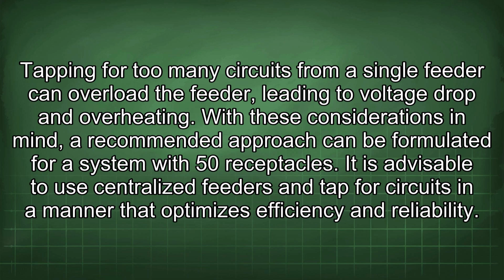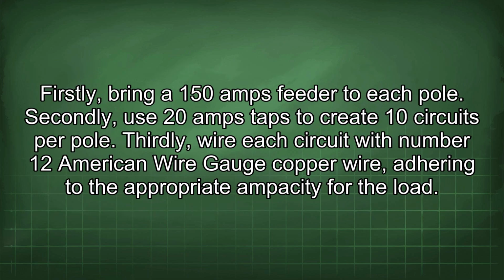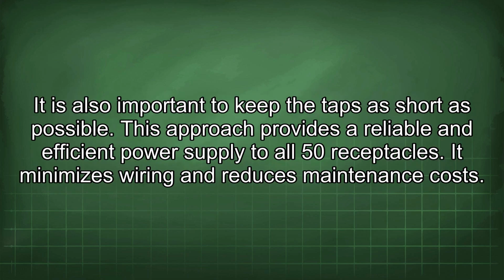It is advisable to use centralized feeders and tap for circuits in a manner that optimizes efficiency and reliability. Firstly, bring a 150 amp feeder to each pole. Secondly, use 20 amp taps to create 10 circuits per pole. Thirdly, wire each circuit with number 12 American wire gauge copper wire, adhering to the appropriate ampacity for the load. It is also important to keep the taps as short as possible. This approach provides a reliable and efficient power supply to all 50 receptacles. It minimizes wiring and reduces maintenance costs.